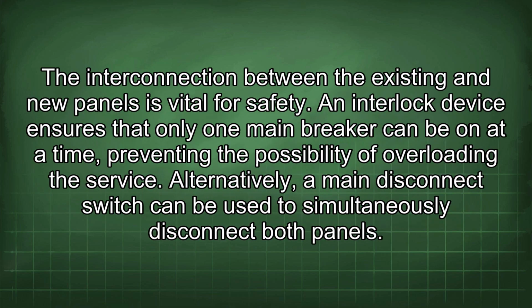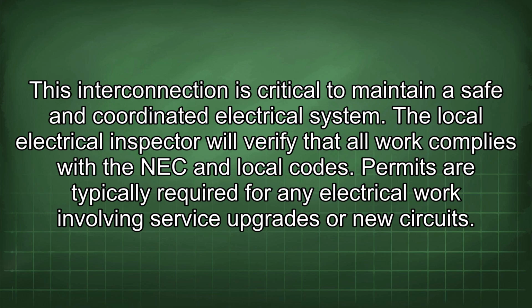The interconnection between the existing and new panels is vital for safety. An interlock device ensures that only one main breaker can be on at a time, preventing the possibility of overloading the service. Alternatively, a main disconnect switch can be used to simultaneously disconnect both panels. This interconnection is critical to maintain a safe and coordinated electrical system.